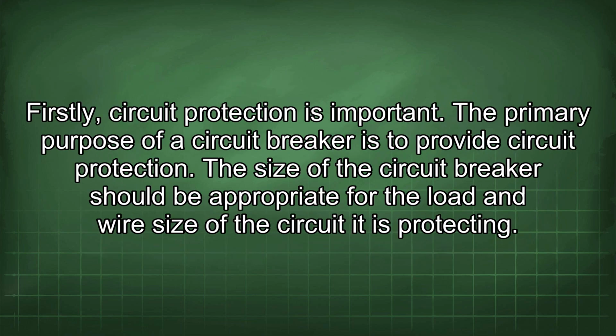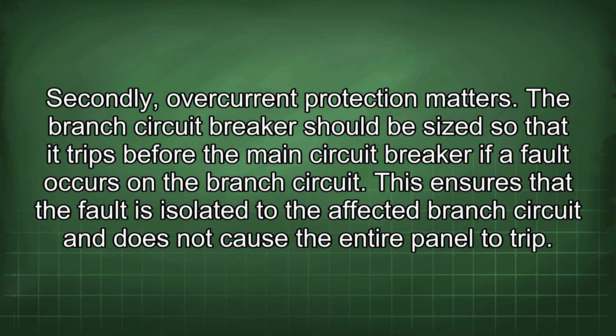Firstly, circuit protection is important. The primary purpose of a circuit breaker is to provide circuit protection. The size of the circuit breaker should be appropriate for the load and wire size of the circuit it is protecting. Secondly, overcurrent protection matters. The branch circuit breaker should be sized so that it trips before the main circuit breaker if a fault occurs on the branch circuit. This ensures that the fault is isolated to the affected branch circuit and does not cause the entire panel to trip.